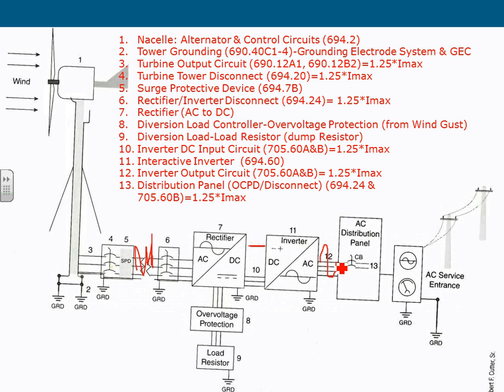The rectifier, inverter, and overvoltage protection can be 2 separate units or 3 separate units or 1 unit. There's technology where the inverter and rectifier are one big unit, or it could be 2 different units with the overvoltage protection as part of your rectification system. The rectifier gets rid of the voltage fluctuations. Your AC voltage fluctuations, when they get to the rectifier, they're gone. You've got a flat DC voltage.